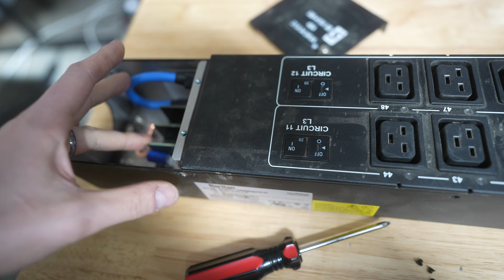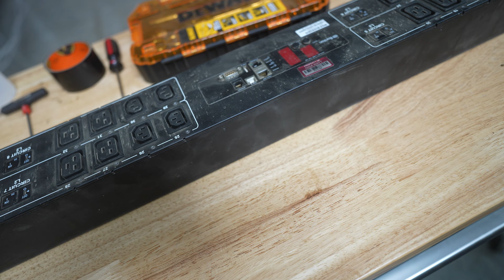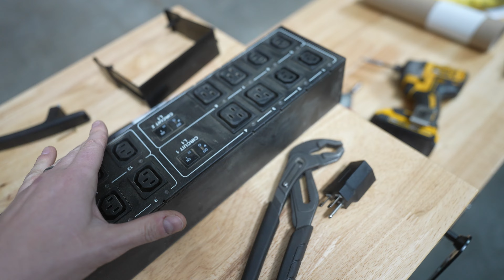To do that, you have to calculate what your load is going to be from each miner. The load from our miners is about 2,200 watts. We don't know for sure yet. So what you do is you take 35,000, divide by 22, and that'll give you how many miners you can load onto this PDU. The PDU is going to be attached to our racks, and we're just going to be plugging in. We'll space it out as we go, so probably plug in 1, 2 here, 1 here, maybe 1, 2 here, 1 here, and so on until we fill up 35,000. Again, we just divide 35,000 by 2,200, and then we know how many we're going to be loading on this guy. So that's how you do that.